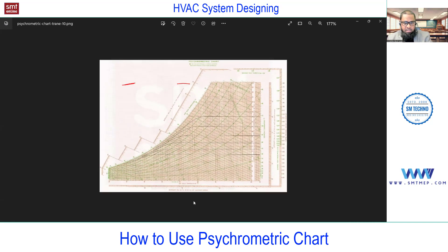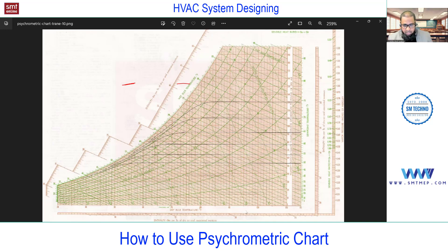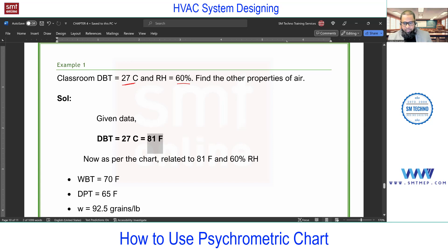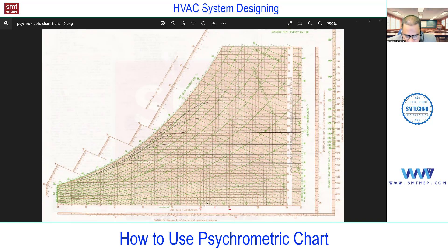This manual chart is from Trane and based on the English system (IP units). A unit conversion is required — 27°C converted to Fahrenheit using F = 1.8C + 32 gives approximately 81°F. So I have two properties: 81°F dry bulb and 60% RH. On the chart, reading between 80 and 90, each division is one unit, so I can identify 81 on the horizontal scale.